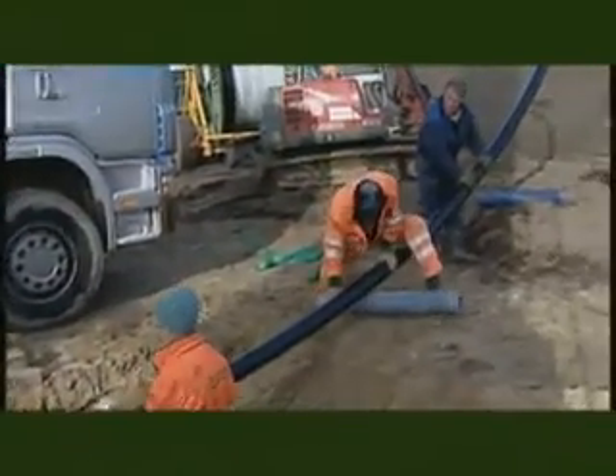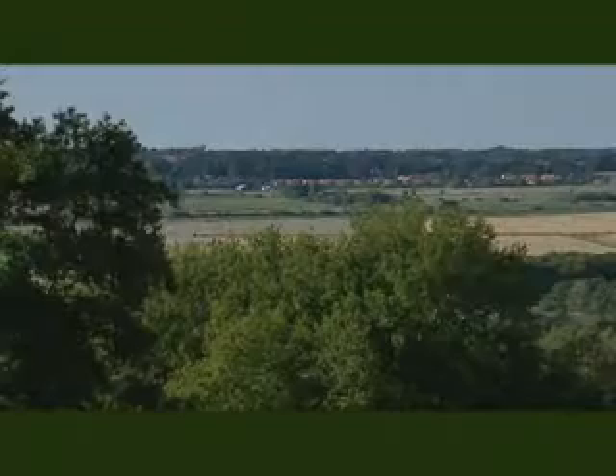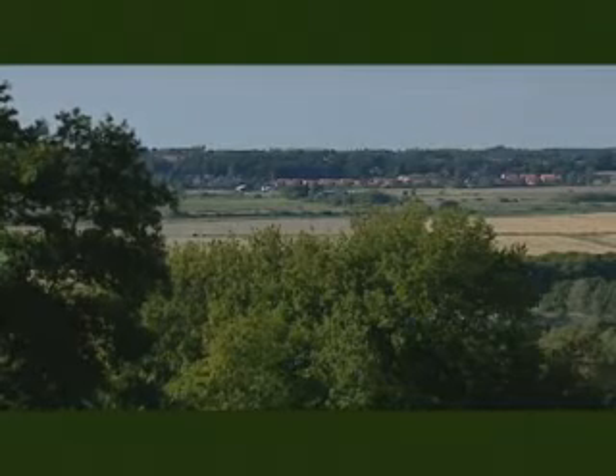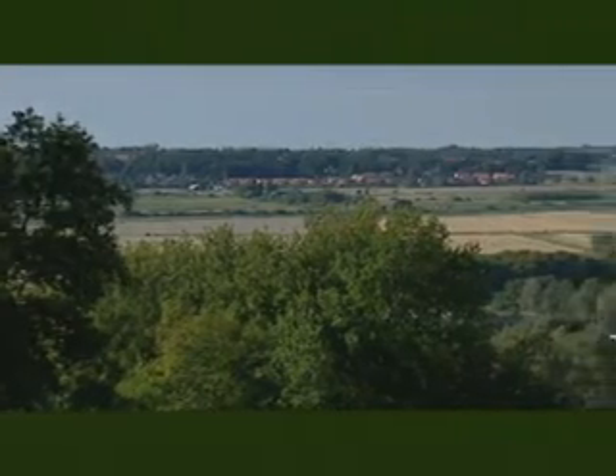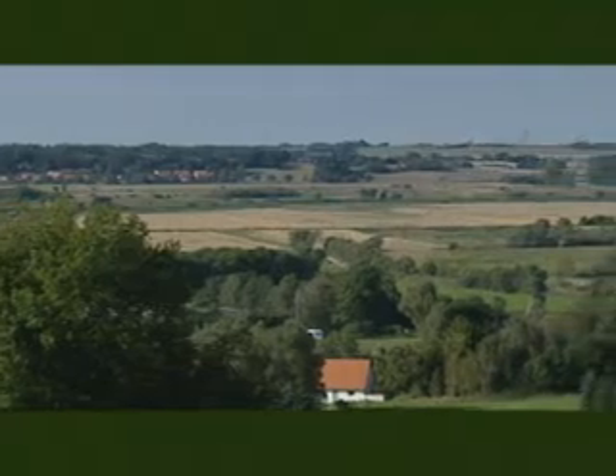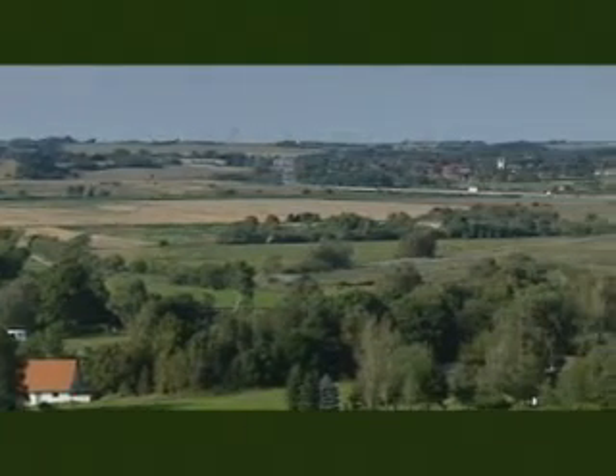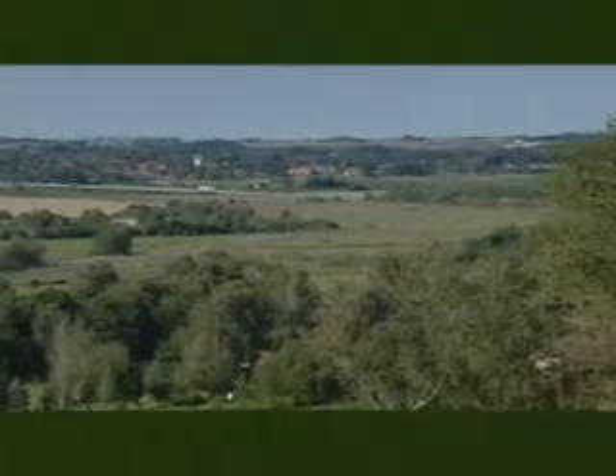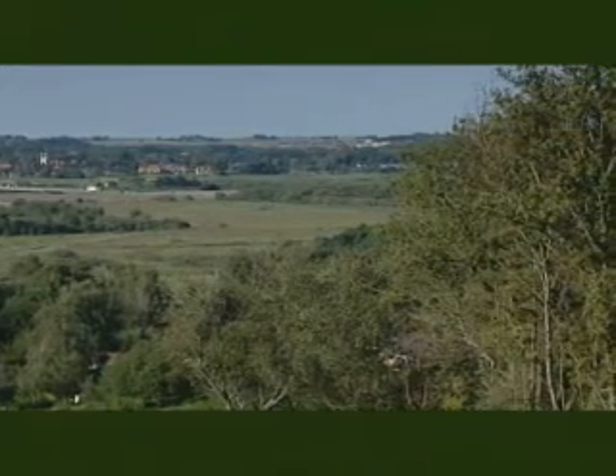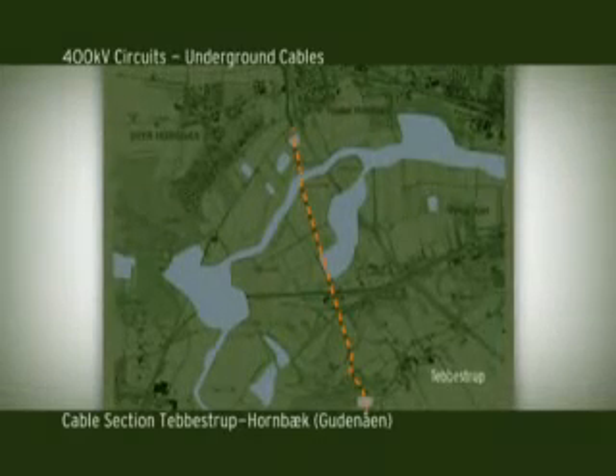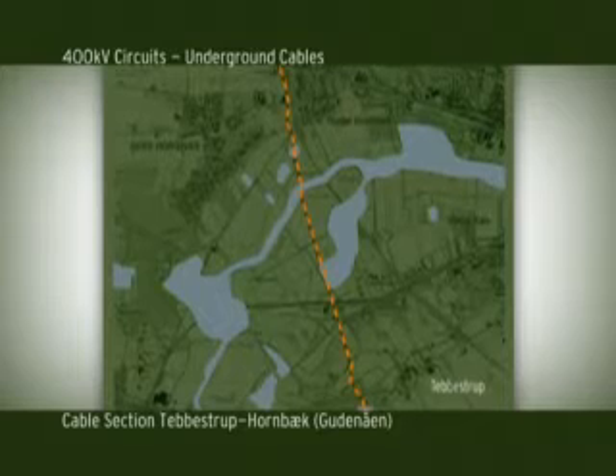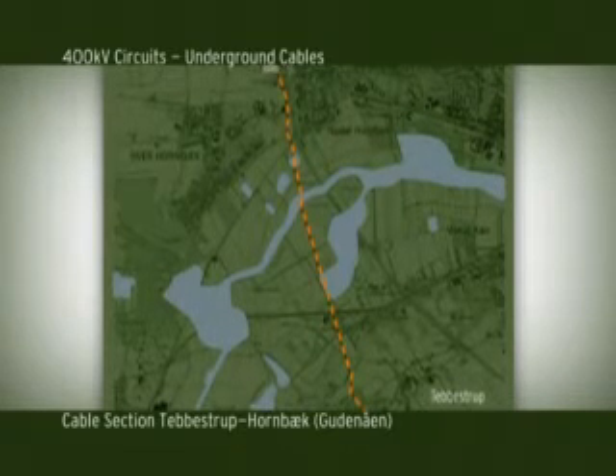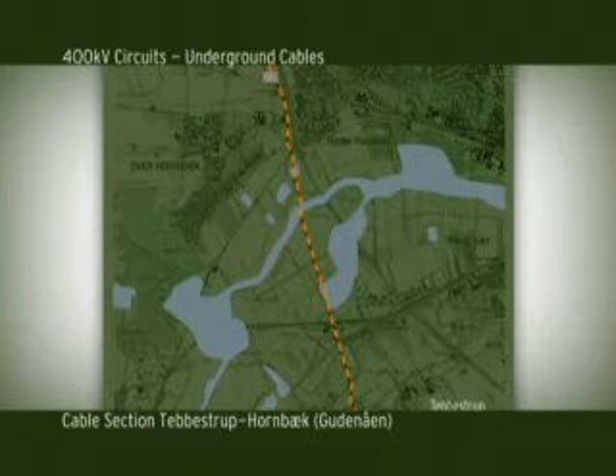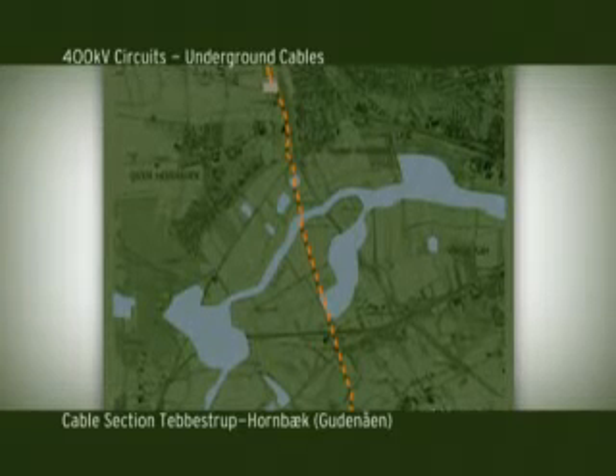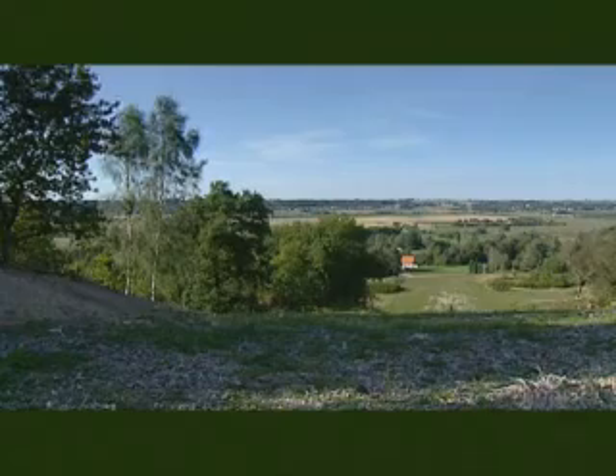Cables are laid along 14.5 kilometres of the connection in 3 sections. A couple of kilometres south of the River Gudenå at Randers, a cable transition compound is built at Tebbestrup. Here the line changes from being an overhead line to underground cables. From Tebbestrup to the cable transition compound Hornbæk, 2 400 kV circuits are buried, plus a 150 kV circuit, as well as 1 or 2 60 kV circuits on part of the section. The section from Tebbestrup to Hornbæk is 4.5 kilometres long.